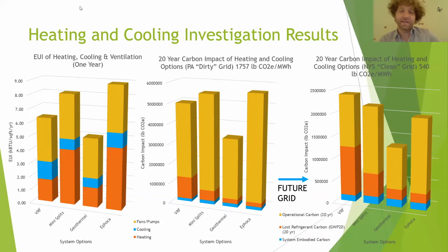You can see that the relative carbon impact changes as the grid gets cleaner, because different things become more important, or they become more of the carbon pie. VRF looks pretty good when you have a dirty grid, because your operational carbon is the biggest piece of the pie. But as the grid gets cleaner, or you add solar and batteries to your building, the refrigerant becomes more of an impact. So all of a sudden, when you have a clean grid, VRF starts looking pretty bad for carbon because of all the refrigerant leaking into the environment. So you can see the trend actually changes.